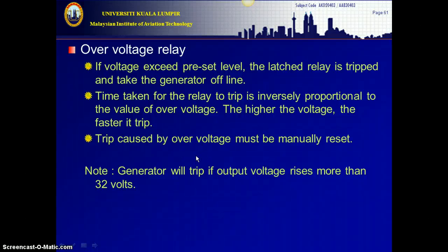This video will discuss the overvoltage relay, another name for which is overvoltage protection. Overvoltage is a condition which could happen in a generating system in the event of a fault in the field excitation circuit. For example, internal grounding of the field winding or an open circuit in the voltage regulator sensing line. Devices are therefore necessary to protect consumer equipment against voltage higher than those at which they are normally designed to operate. The method adopted varies between aircraft systems and also on whether they supply DC or AC.